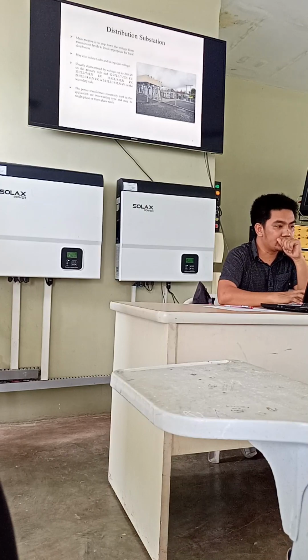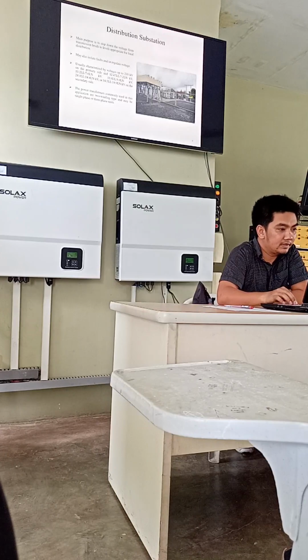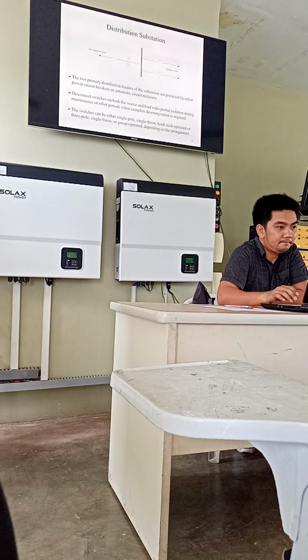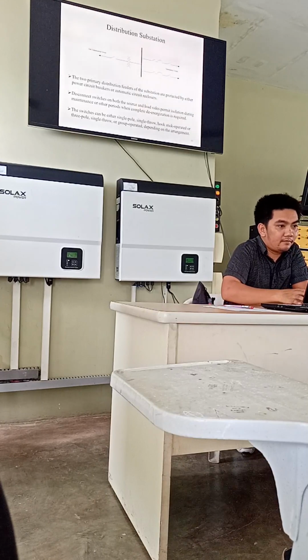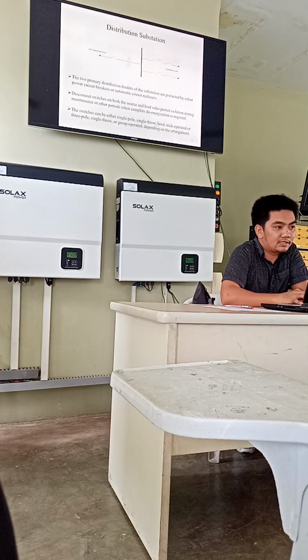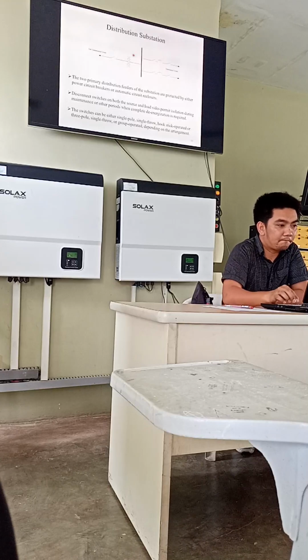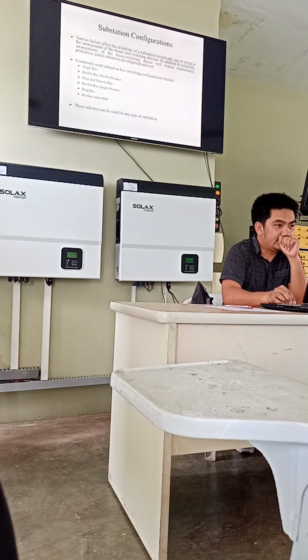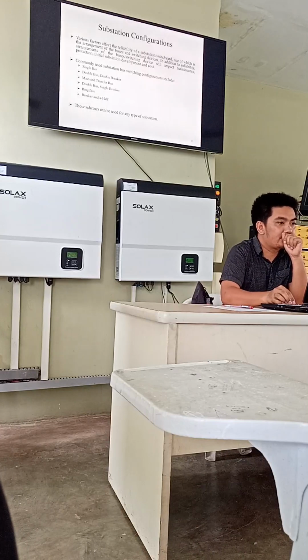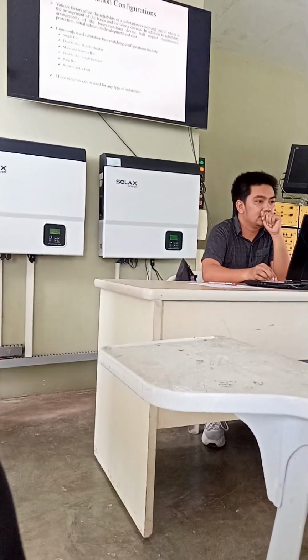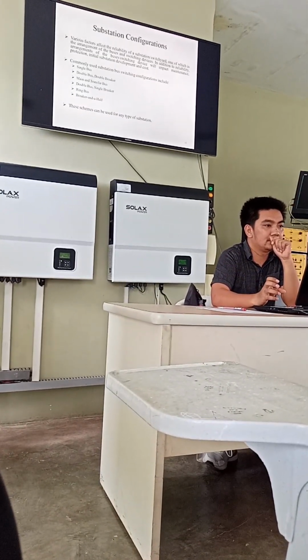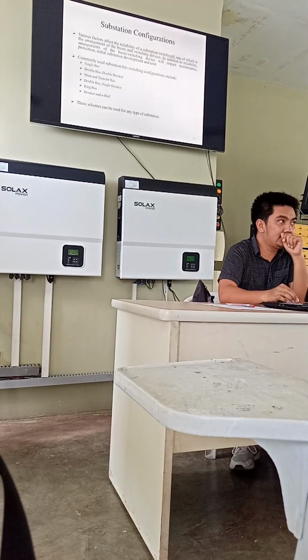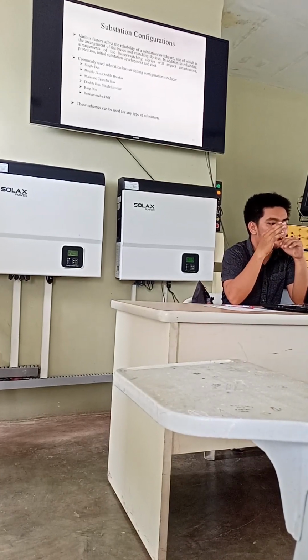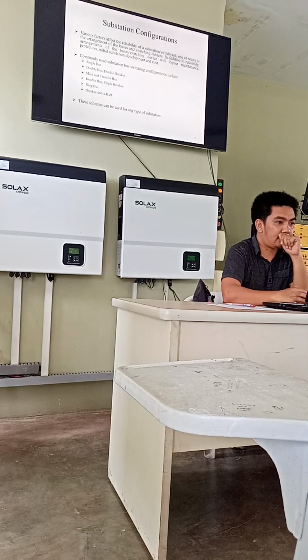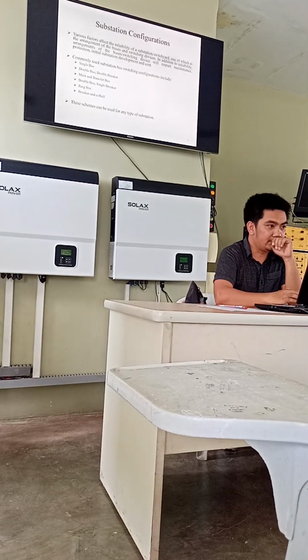So the power transformer commonly used in these applications is a two-winding unit, no? It could be a single-phase or three-phase unit. And this is the typical picture or diagram of the distribution substation from the sub-transmission circuit to the distribution circuits. Now there are different configurations of the substations because basically we treat the substation as the heart and brain of the energy system. It should be protected or well-designed infrastructure, no? So depending on the reliability requirement, we also have appropriate designs for that requirement.